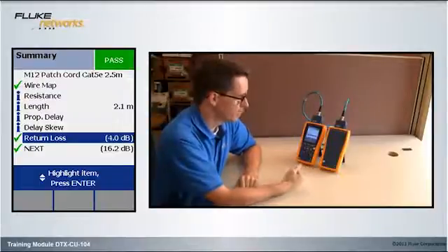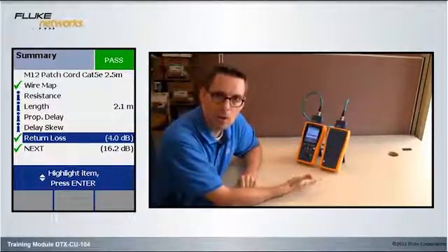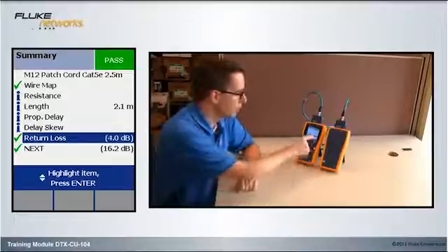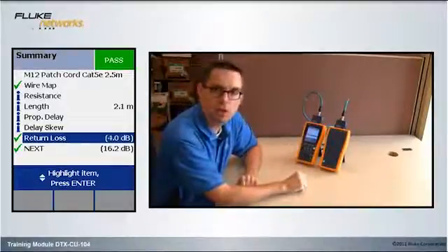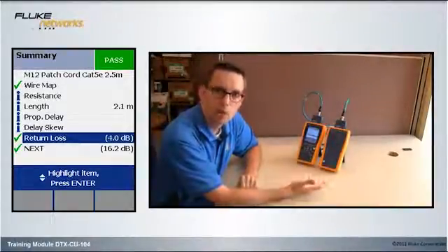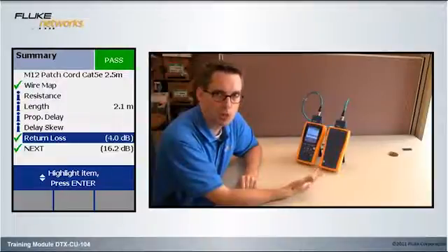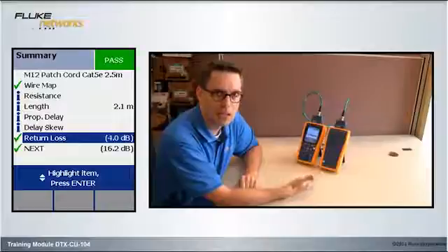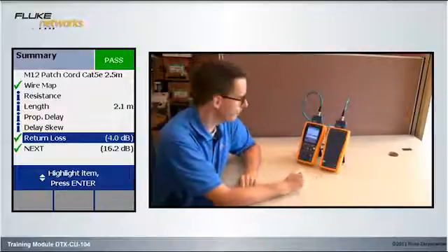Now, what is a good value here? Anything above 0. If it's below 0, you would have seen a fail appear in the top right hand corner here. Do you want to be 0.1 dB? Not really. You really want to be a little bit more above than the standard. The standard is the bare minimum after all.